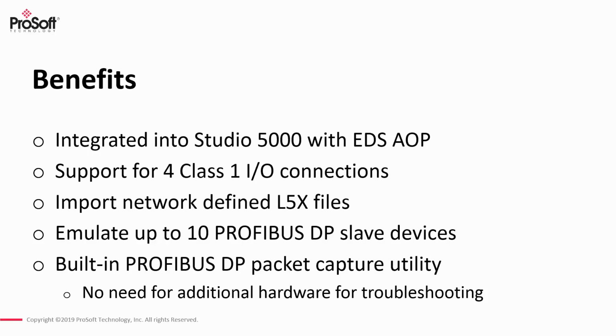Studio 5000 environment. We can emulate up to 10 PROFIBUS DP slave devices, and so one of the things I mentioned earlier was a PROFIBUS DP slave is limited to 244 bytes of cyclic data. So in instances where you needed to transfer more than 244 bytes, typically what you had to do is set up DPV1 messages to do data table reads or data table writes of additional information. This required additional programming on a master device. And so what we do with our slave implementation of this module is we can emulate up to 10 PROFIBUS DP slave devices, each one of those transferring a maximum of 244 bytes. So this gives you high-speed cyclic I/O update rates and eases the configuration and the programming on the master side.